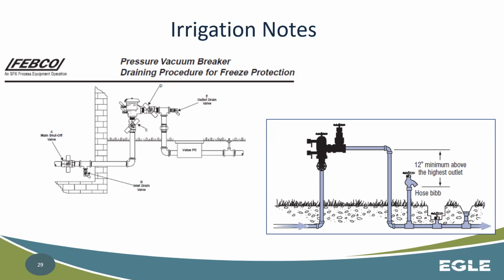And then these are one of the ones that often have winterizing considerations, where I've seen it, they're left over the winter, maybe they weren't drained, and if they freeze up, some of the pipe might get damaged, valves might get damaged, or the spring itself might get locked up or might get knocked loose. All of these are things that can lead it to where it is no longer functioning properly and is not protecting your water system.